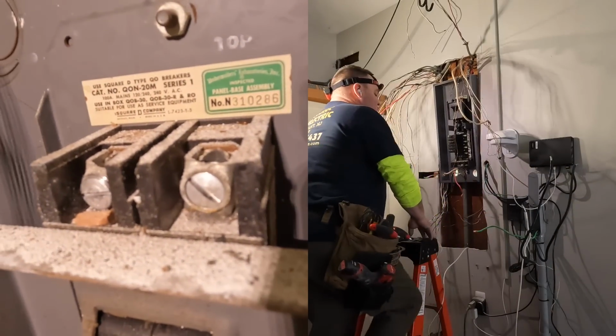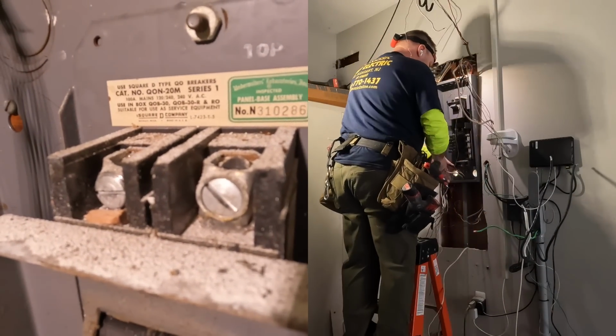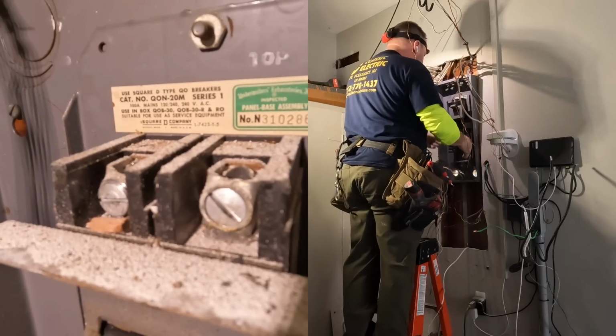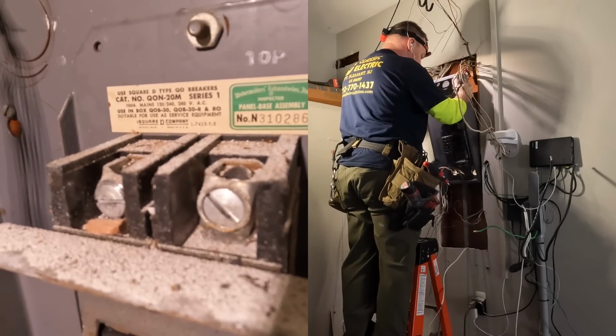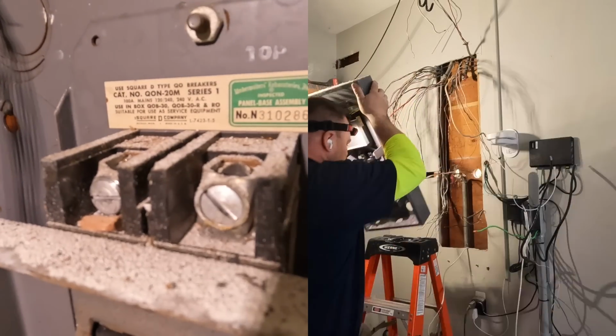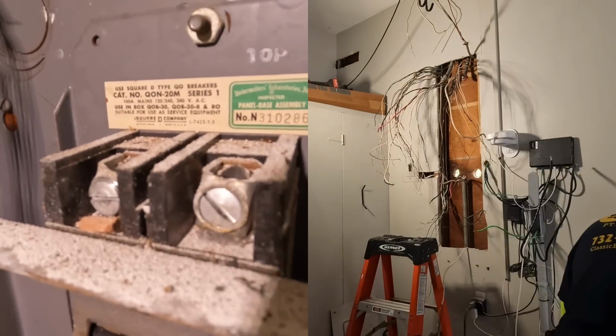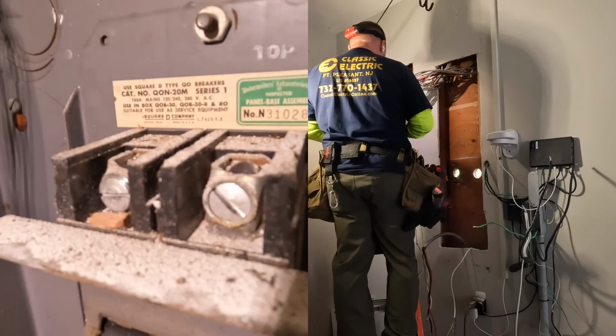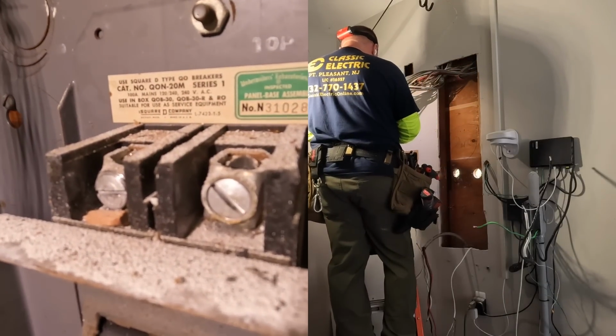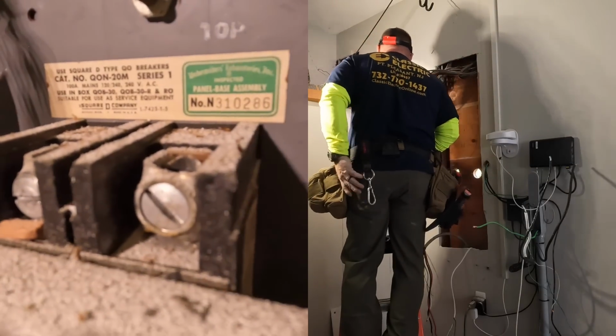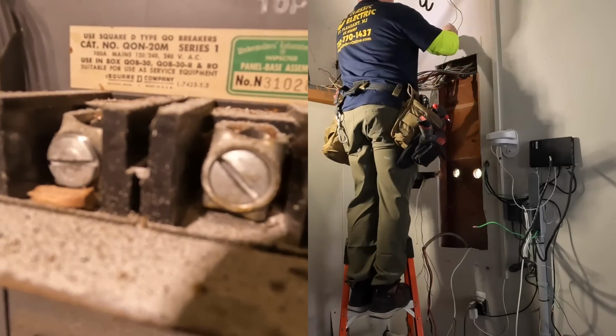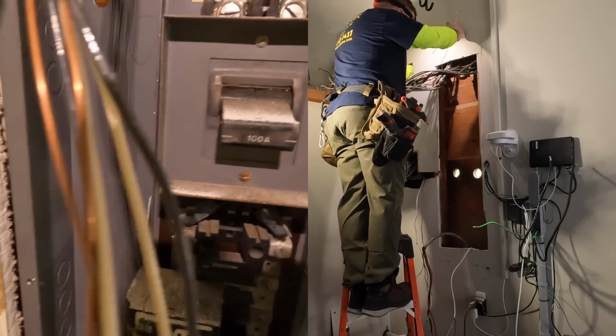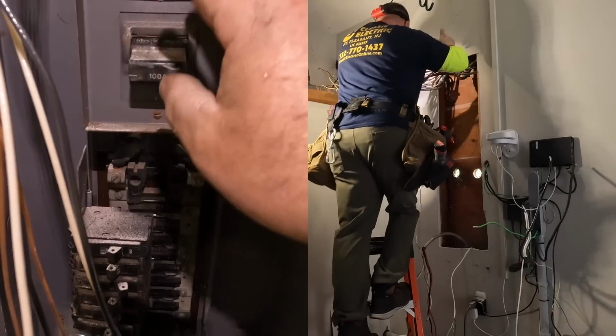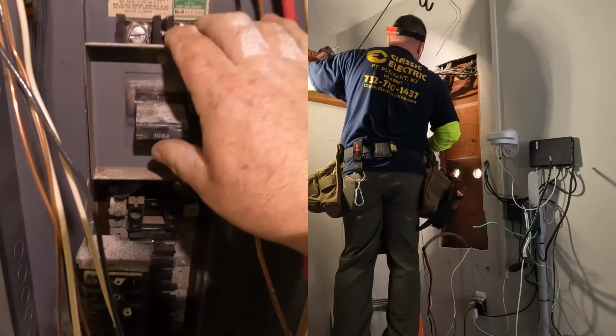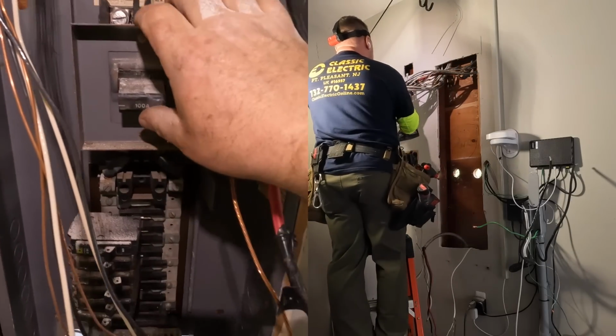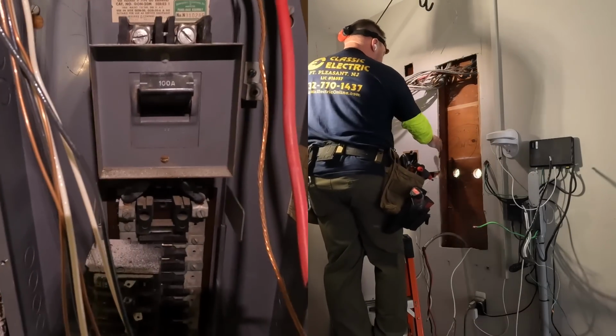Looks like the model uses Square D type QO breakers. Catalog number QON-20M Series 1, 100 amp main lugs, 240 volt alternating current, using box QOB30, suitable for use as service equipment, the Square D Company. Underwriter's Laboratory inspected panel base number. This is it. I don't remember ever seeing an old main breaker like this one, but it's working very well. Sometimes you turn these off, you can't turn them back on. But Square D is definitely some high quality stuff.